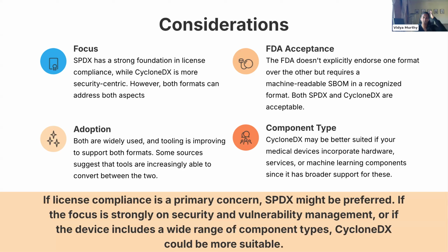So here are the considerations for each of these. SPDX has a really strong foundation in license compliance, which is not one of the things that the FDA expects you to track in your SBOM. However, if you are using it for operational purposes, that might be a way to hit two birds with one stone and track it that way. CycloneDX is definitely more security centric and will also serve that purpose, but it doesn't lend itself to license tracking.